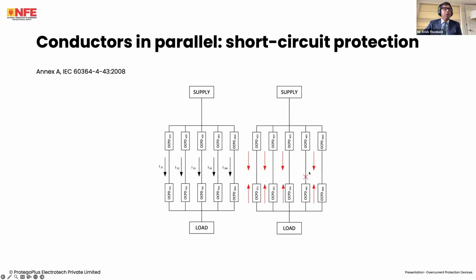The risk that can happen here is that, like I said, current flows from all sides. So we can provide OCPD protection not only on the supply side, but on the load side as well. However, there is another risk of doing this: current will flow from all sides, through here, disconnection will occur, and this run goes dead. But now the other remaining runs are subject to an overload. And if this overload is between the conventional non-fusing current and the conventional disconnection current, this overload can go unnoticed, basically. That is where it can go terribly wrong.